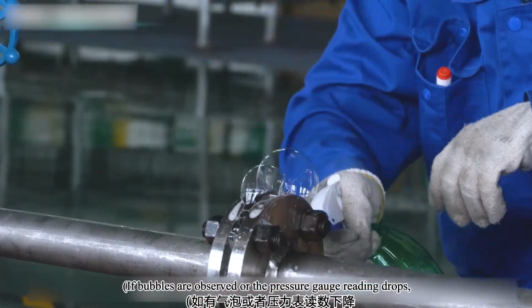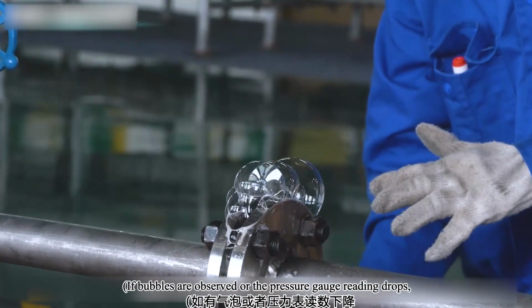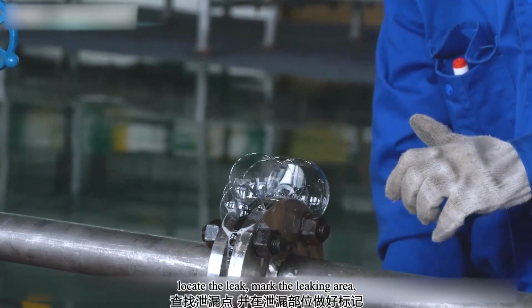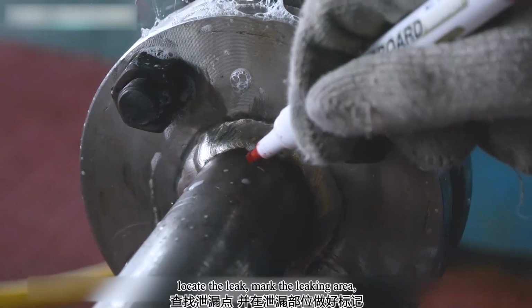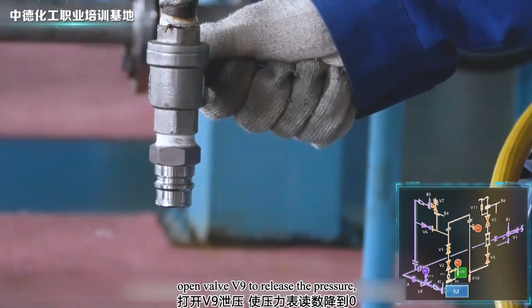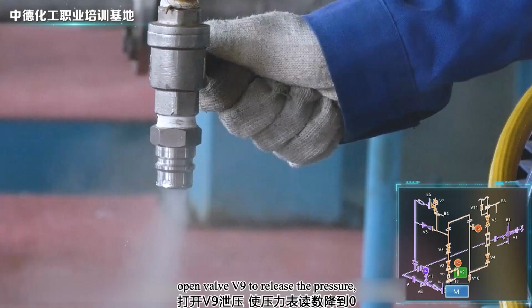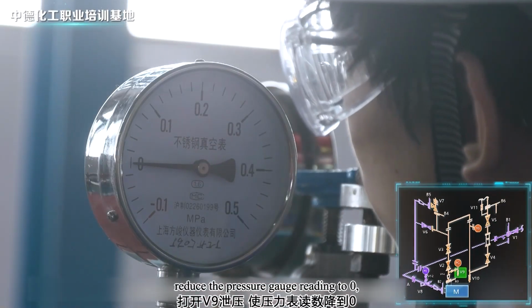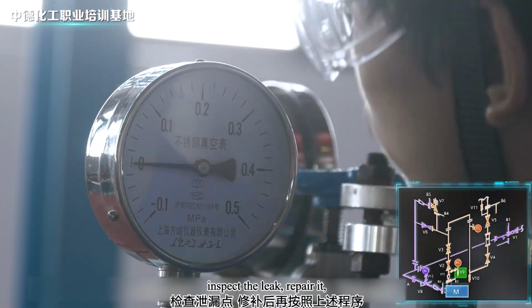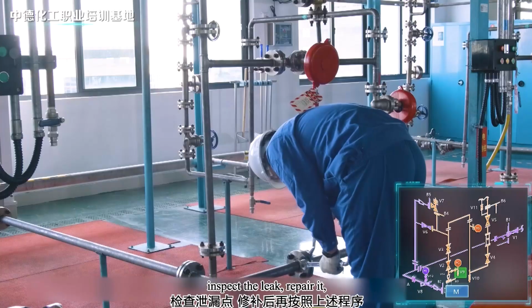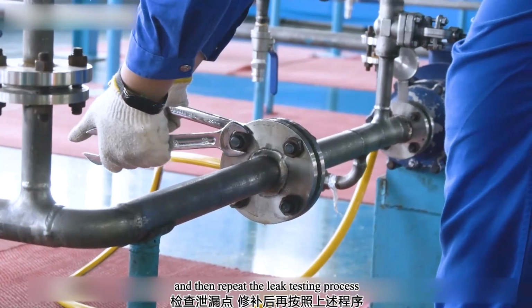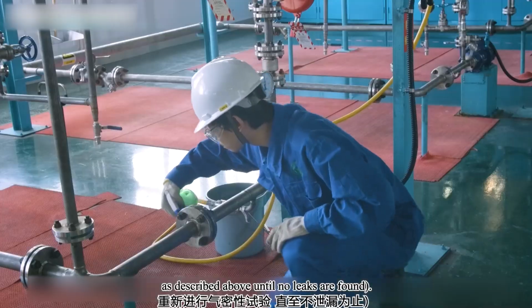If bubbles are observed or the pressure gauge reading drops, locate the leak. Mark the leaking area. Open valve V9 to release the pressure, reduce the pressure gauge reading to 0. Inspect the leak, repair it, and then repeat the leak testing process, as described above, until no leaks are found.